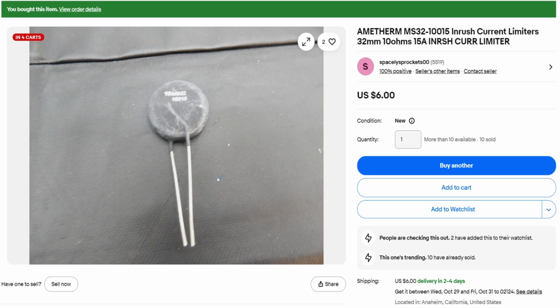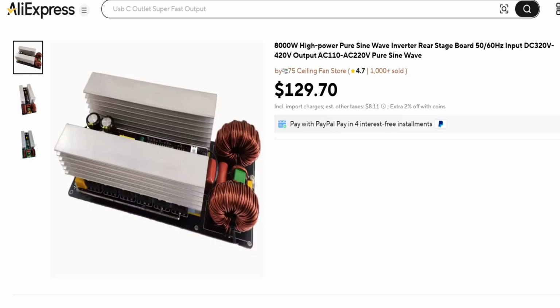One thing you need to be aware of is that this inverter module has capacitors on the input side, 180 microfarads each, times 4, so 720 microfarads at 450 volts rated capacitors. If you hook that up to an enormous battery pack and flip the switch, there's going to be a huge inrush of current into these capacitors.